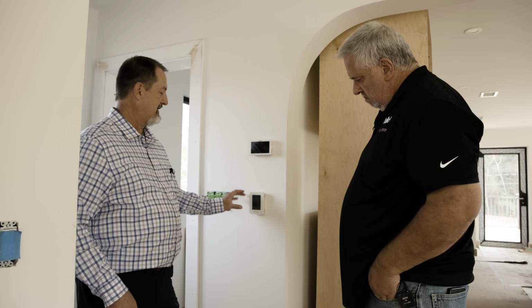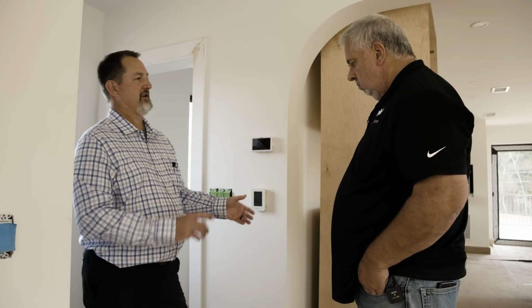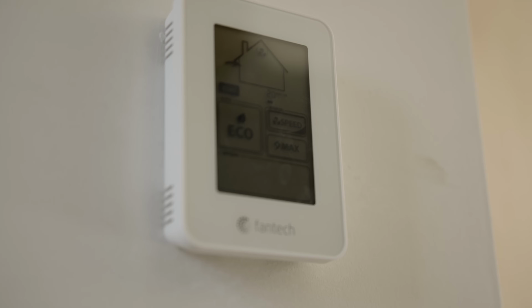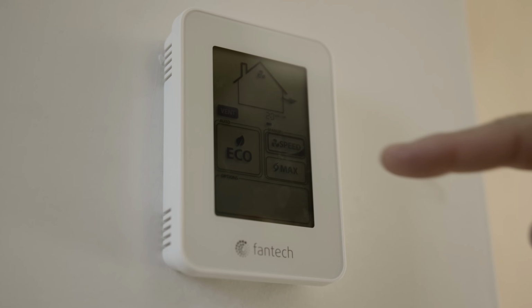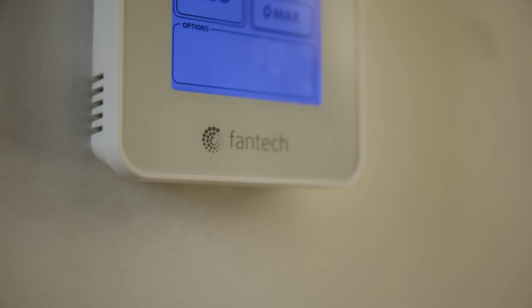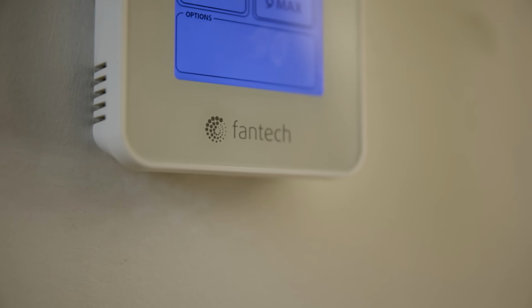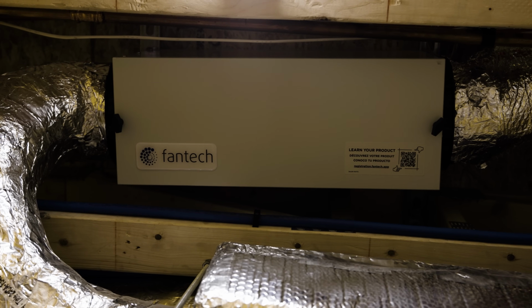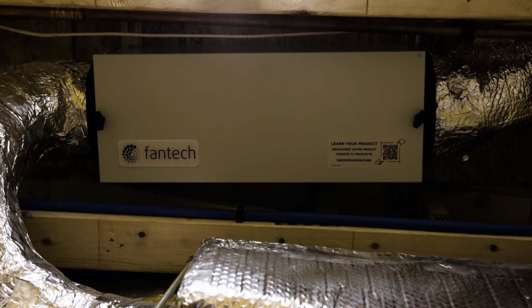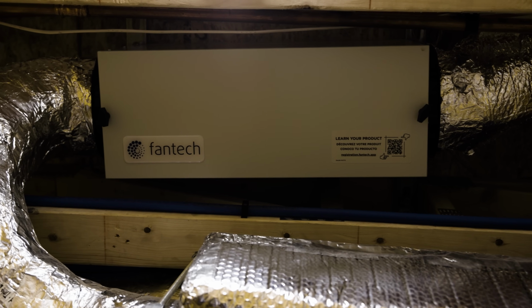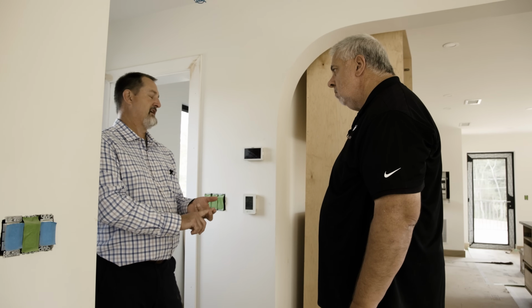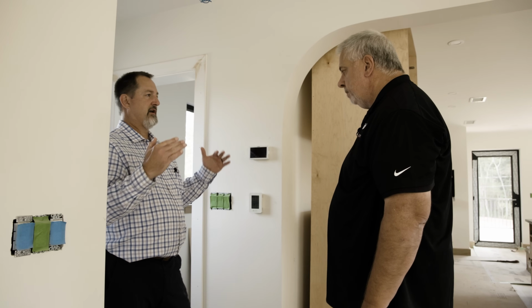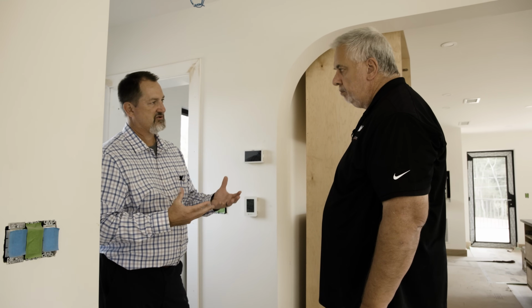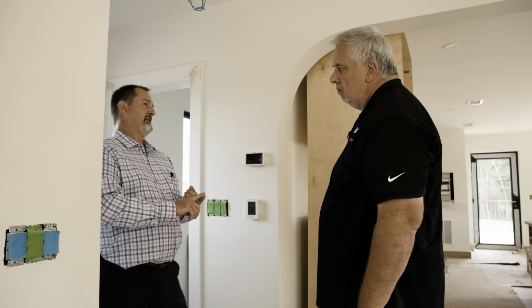And when I say that, it's sensing total VOCs in the home. What it does is it establishes a baseline—it learns what's normal in this home, and hopefully normal is good. So you might have your ERV set up, and what we always recommend is sizing that unit to deliver the CFM you want continuously, running on low speed. There's a couple reasons for that. One, on low speed it's at its most efficient, because you've got a slower airflow through the heat exchangers, so you get way better recovery. Secondly, it gives you the ability to bump up that CFM if you need it.